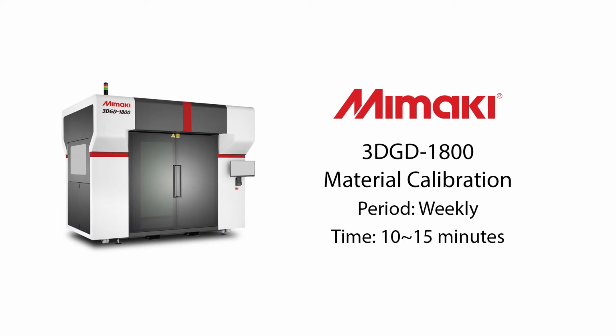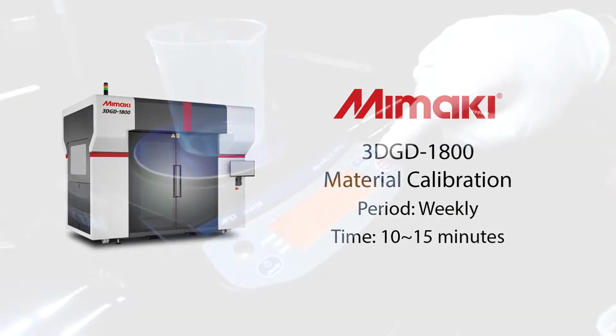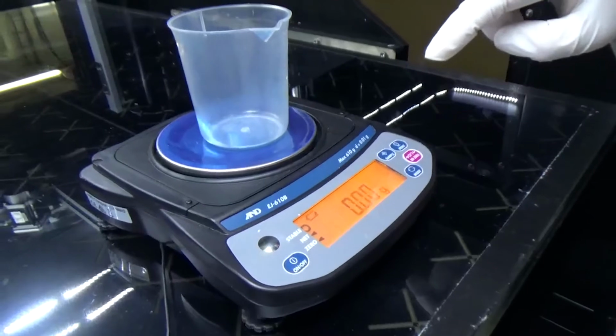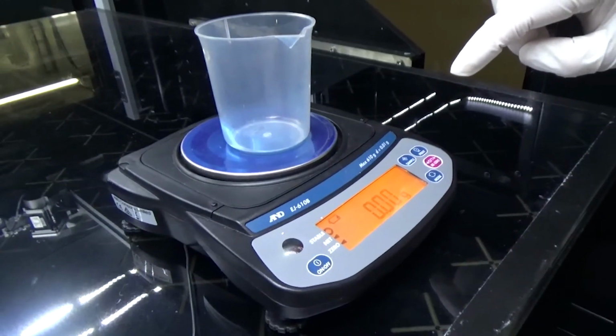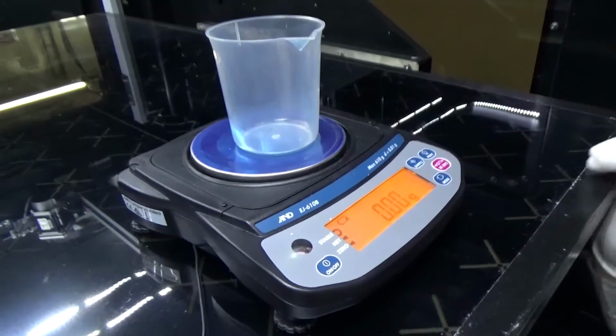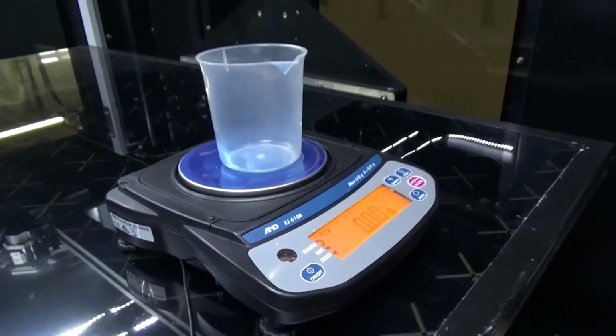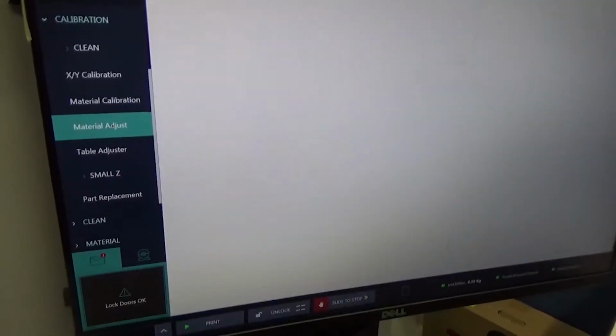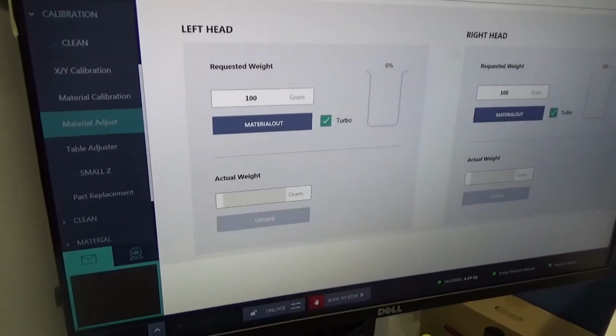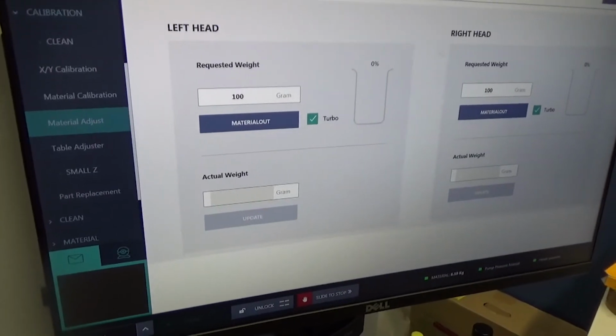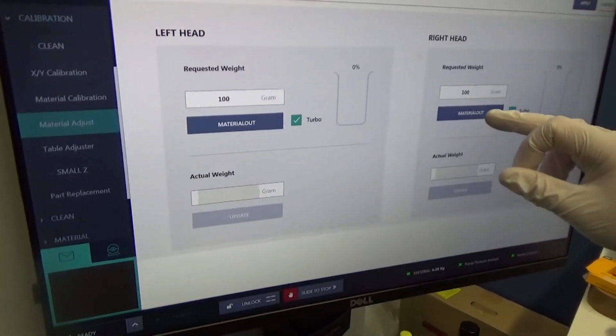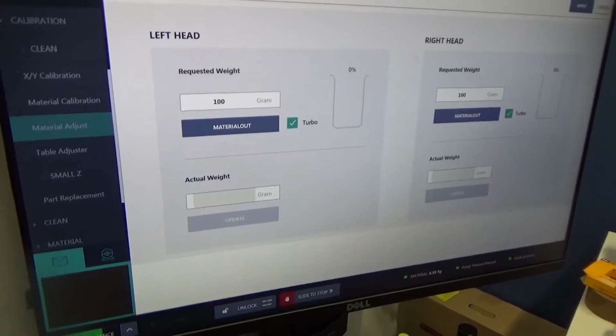Material calibration. You will need a digital scale and a disposable cup. Place the scale and cup under the print head and zero the scale. First, lock the doors and select Material Adjust from the calibration menu. Check that the cup is positioned under the head and select Material Out.